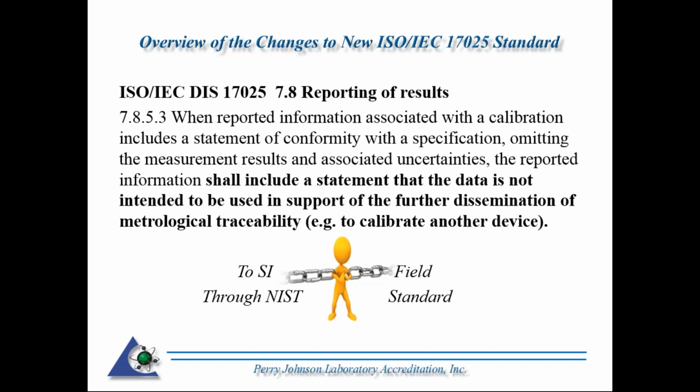If you report a calibration without an actual uncertainty, and that calibration is going to be used for other calibrations, that's not going to be considered a traceable calibration because it does not have an associated measurement uncertainty. And actually, if you're an accredited calibration lab, that's something you would definitely need because you would be promoting traceability. That would be a component of yours. Sort of getting a little bit off base there. But basically, if it's not included right now, that statement needs to be put on there and should be clarified during contract review.